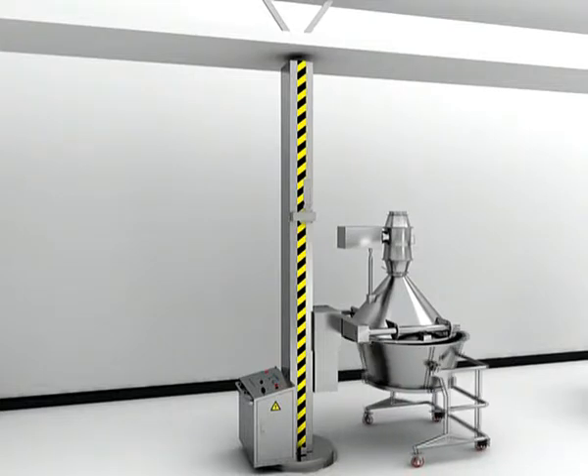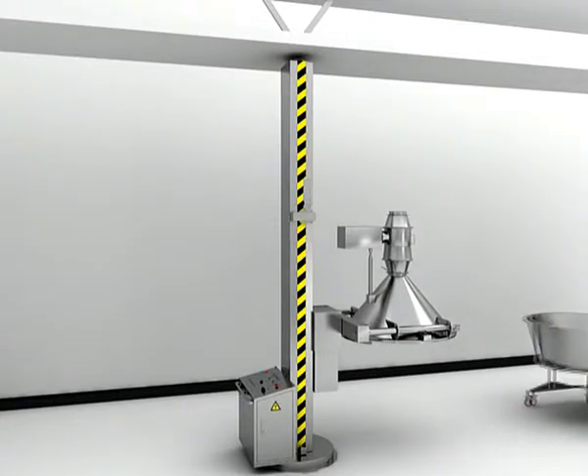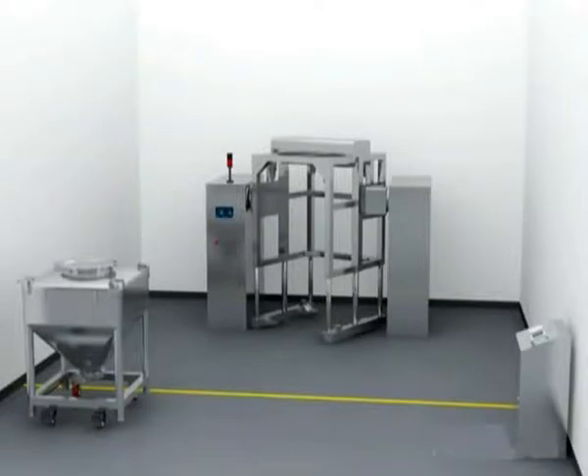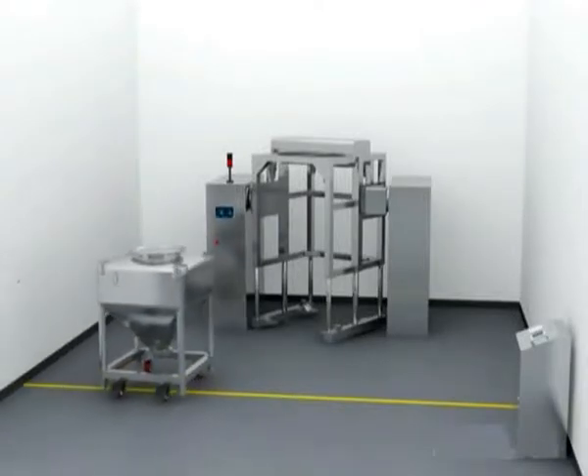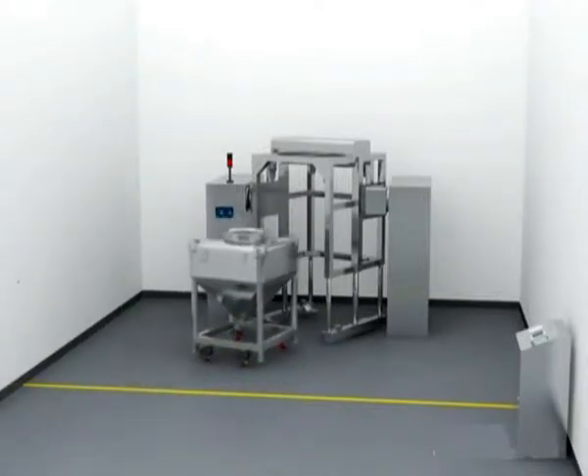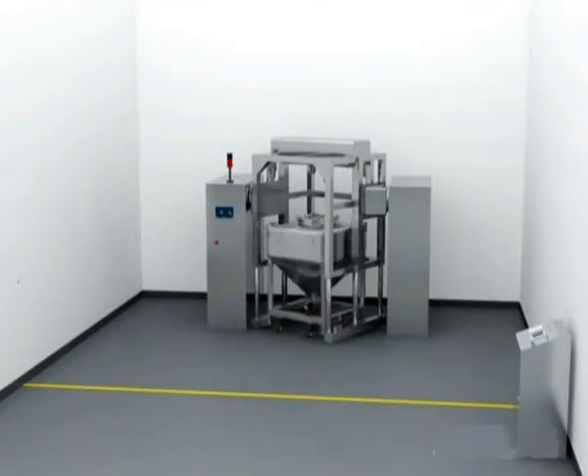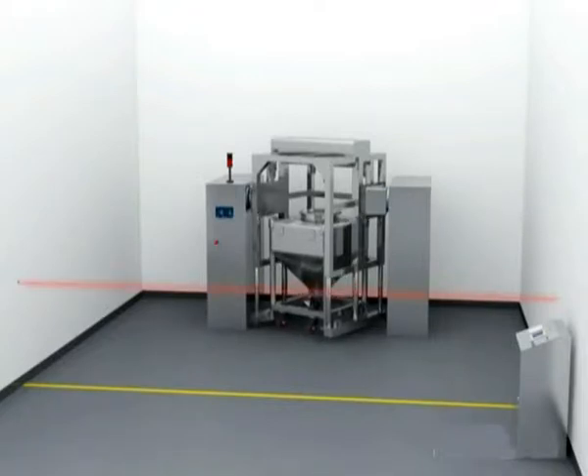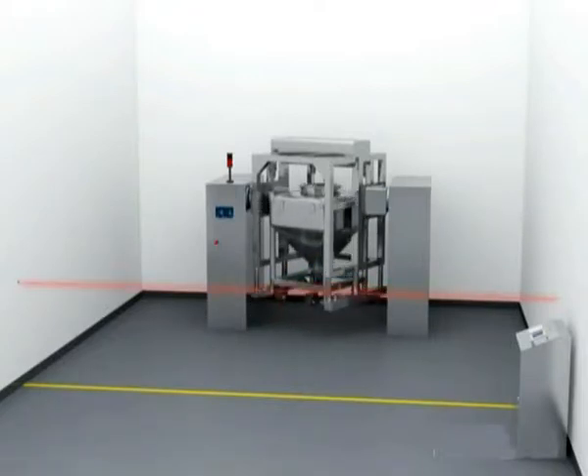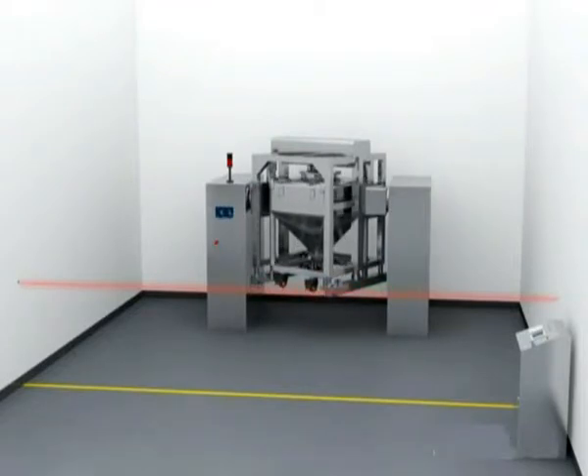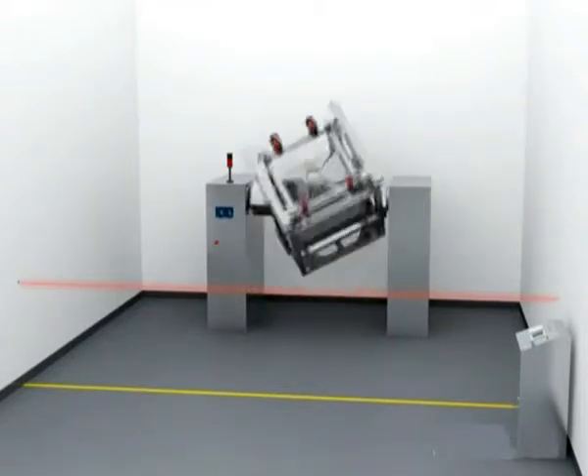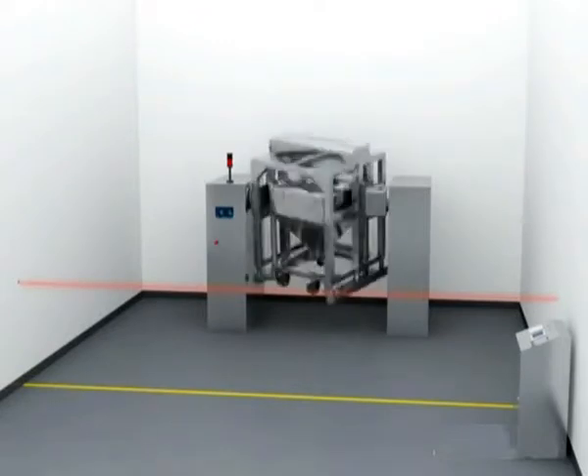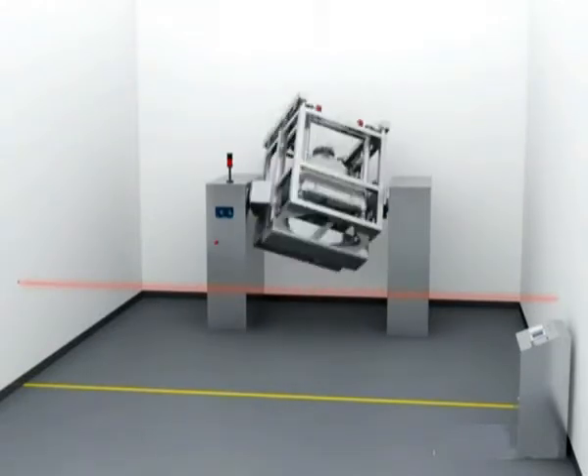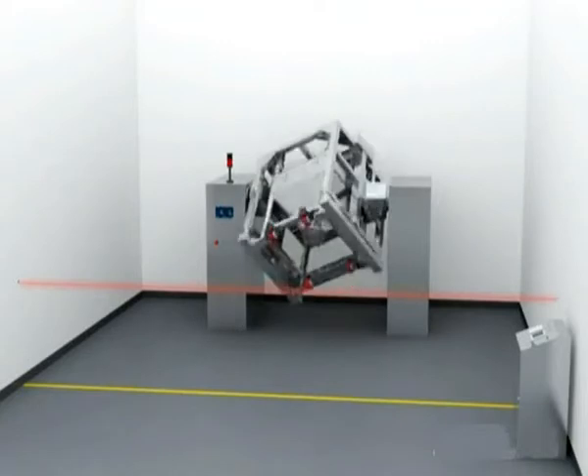Now push the loaded bin into the bin blender for the mixing work. First, push the loaded bin into the bin blender frame. Then start the control procedure. The infrared safety sensor is activated. Then the bin is lifted to the set position and tightly clamped, and the bin blender can start working according to the preset mixing time and speed. When mixing is over, the bin will automatically orientate to a vertical position, then go down to the ground.